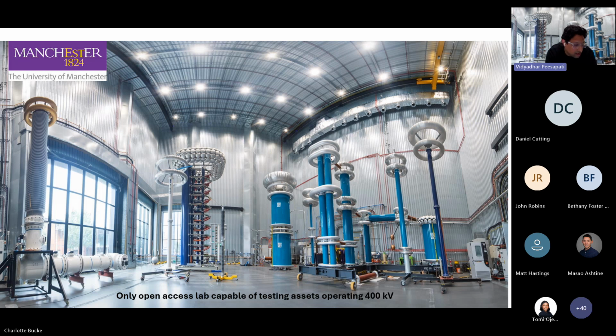There is an 800 kV RMS AC test set with 2 amps. The UK network is 400 kV, which is around 230 kV RMS. This test set does 800,000 volts RMS, so you can push your asset up to three times more. We also have a DC test set that does 600 kV DC testing. The lab is the largest open access facility within the UK, and it's not far from Piccadilly, so it's in the city centre as well.